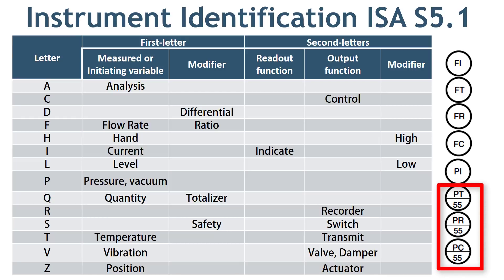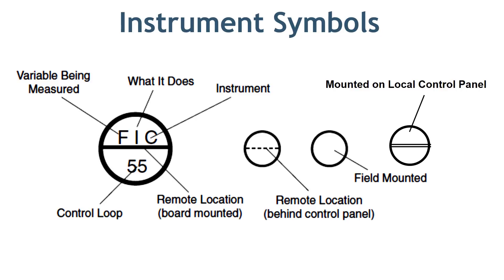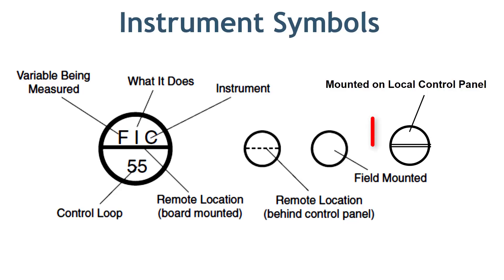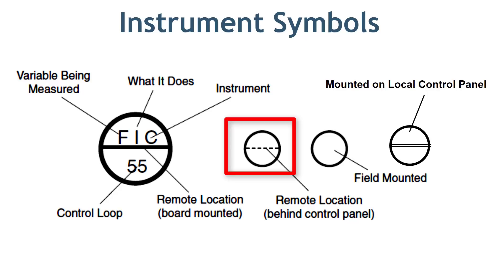In the next slide, I will explain the meaning of the horizontal line on the instrument bubble. If there is a single horizontal line, that means the instrument is located on the main control panel and accessible to the panel operator. No horizontal line means the instrument is installed in the field near the process and is accessible to the field operator. A double horizontal line means the instrument is installed on a secondary satellite local panel in the field. The last type is the instrument bubble with a single dashed horizontal line, which is used for instruments that are inaccessible in the field or hidden or password-protected on the control system.